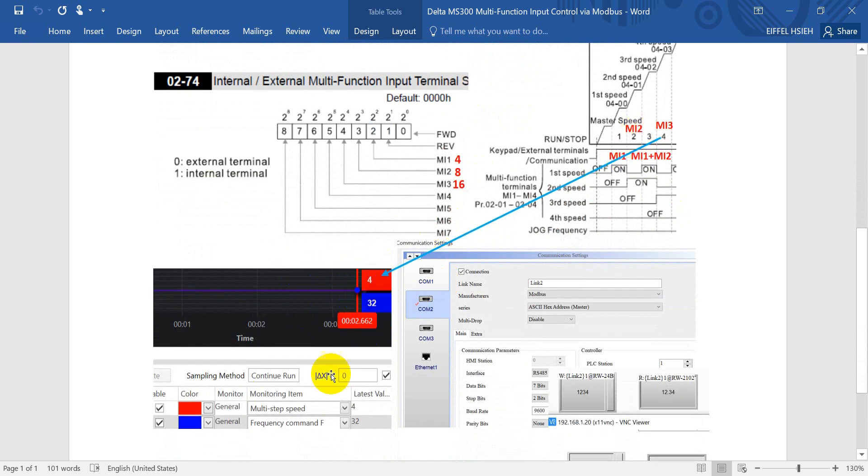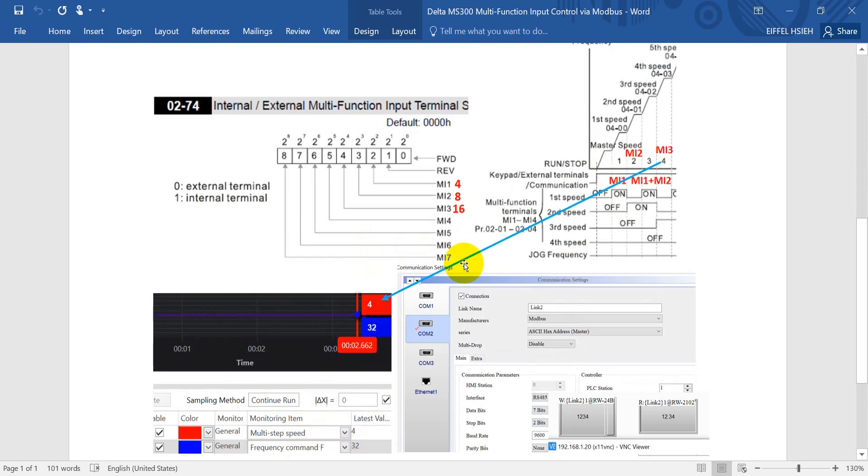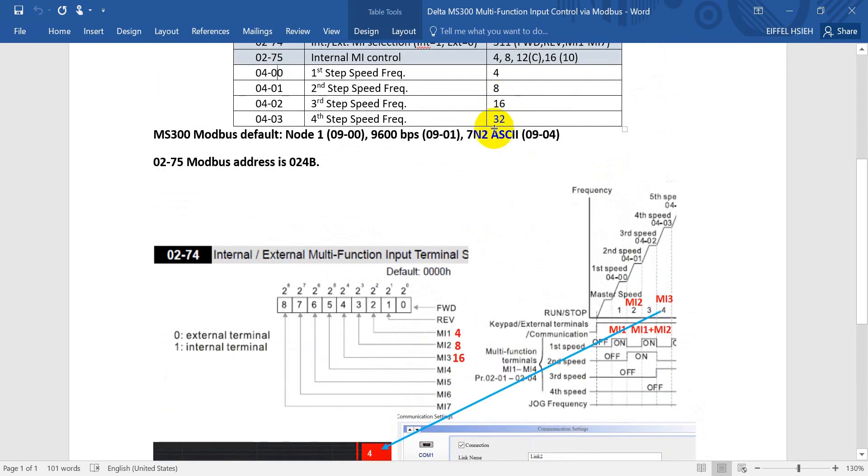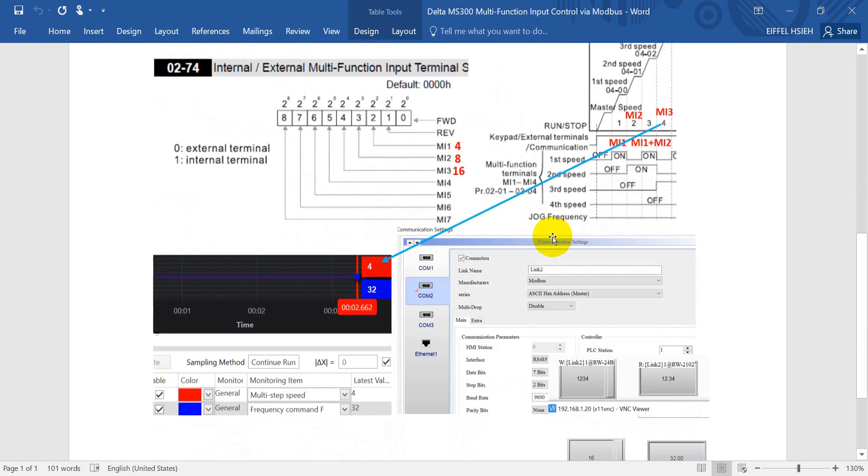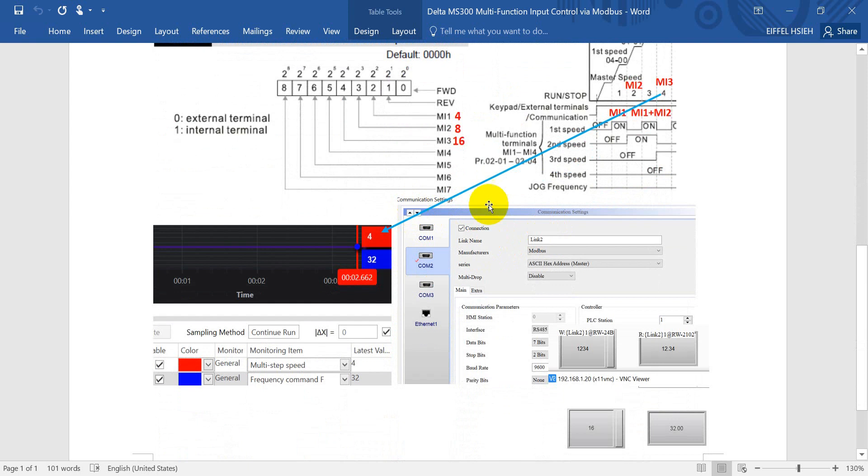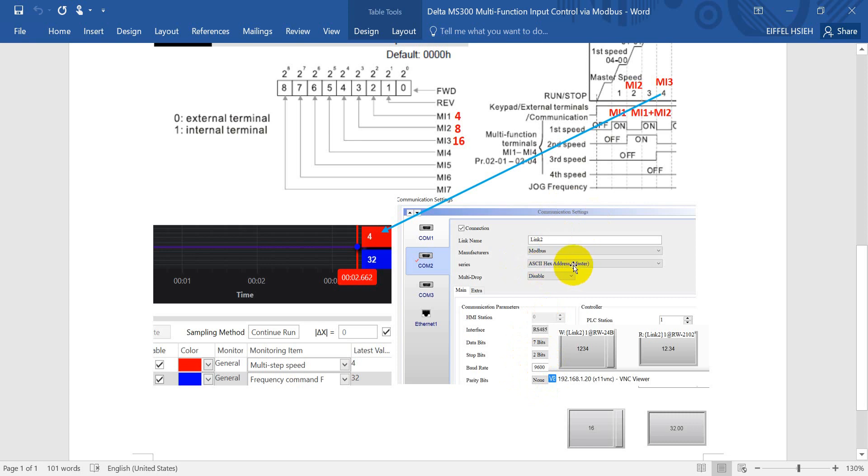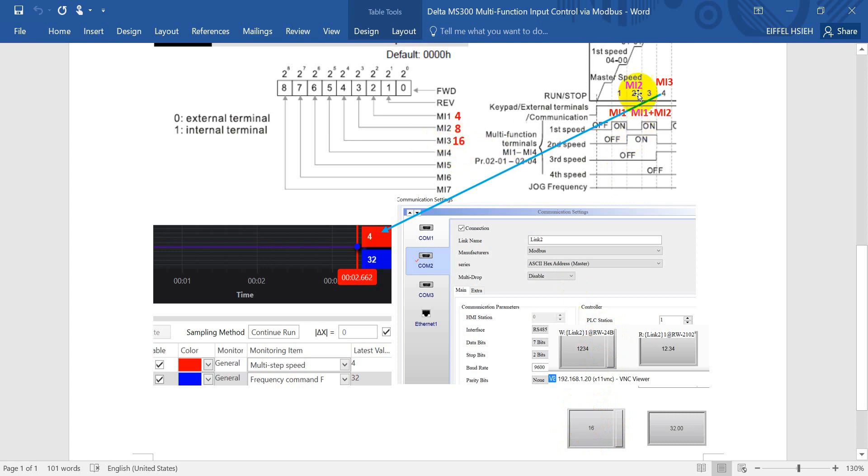Then I will also show you from the ISPsoft designer the scope function. You can see here we monitor with the multi-step speed. You can see the value will show 4 and the frequency command will show 32 as mentioned here. I also control here from the HMI. We will select the COM port and define the protocol as ASCII-7N2, 9600 baud. Here we will select the ASCII hex address. This one, as I mentioned, for control parameter P02-75, the Modbus address would be 024B. If we enter 16, 16 means our MI3 is on, so you will go to 32.